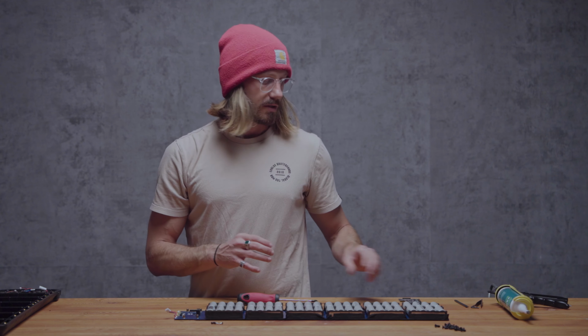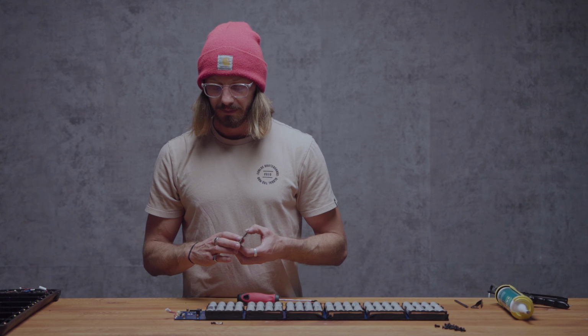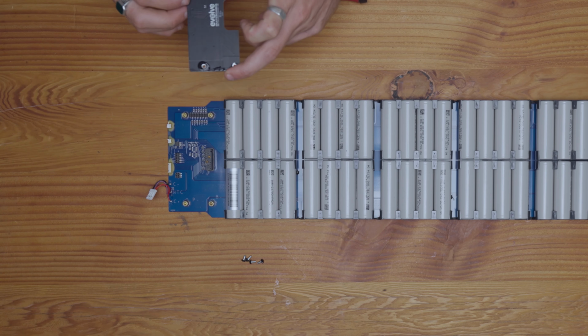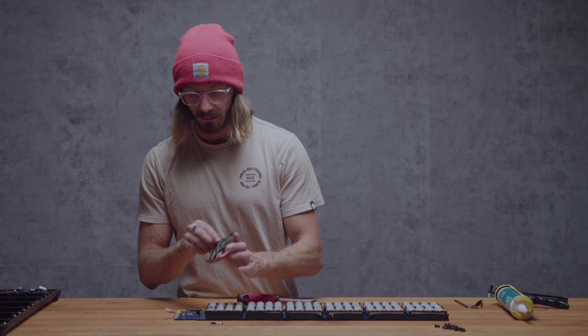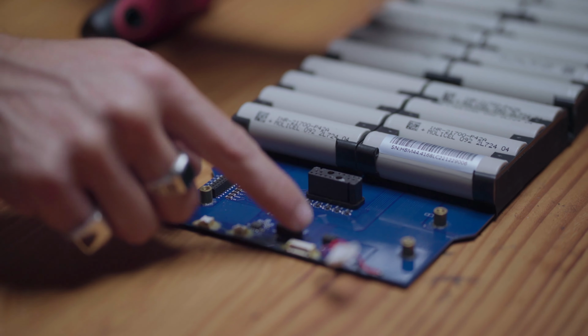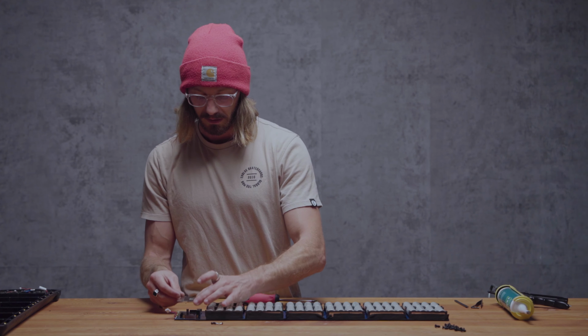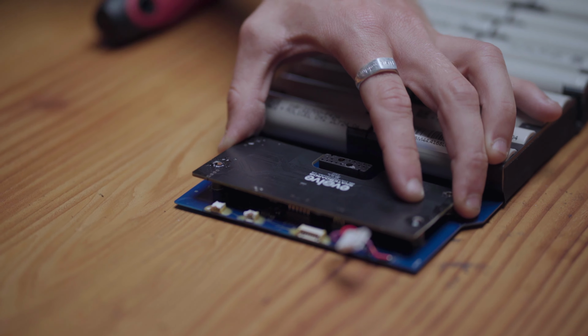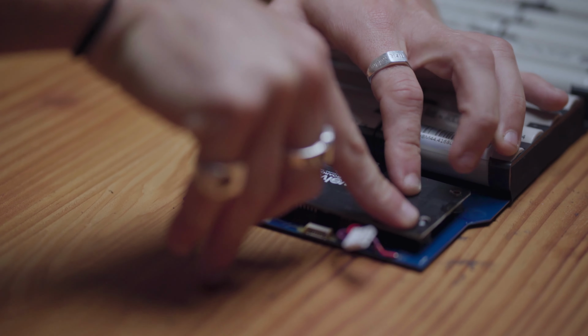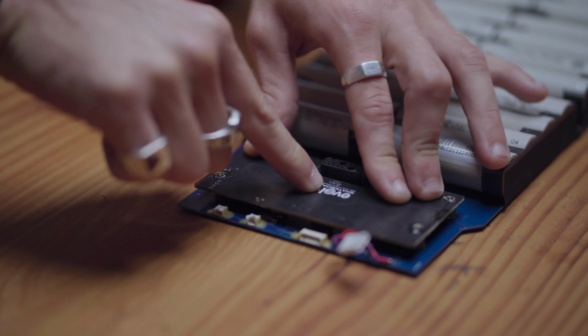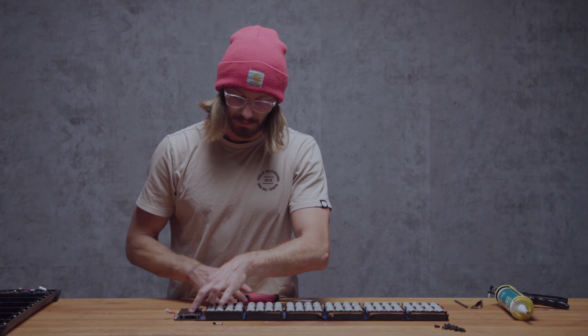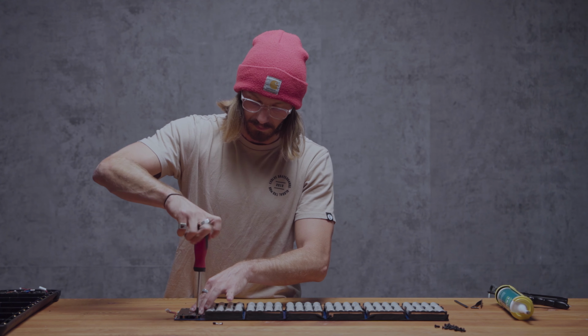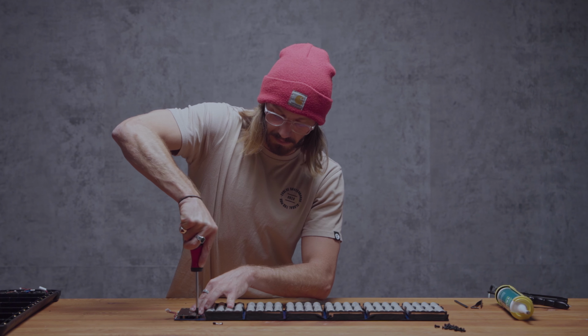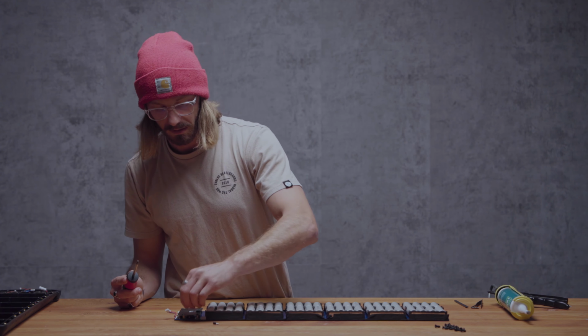So now we're going to go ahead and reinstall our replacement BMS. Essentially the same process in reverse order. First thing is putting the BMS back onto the PCB. Again, we want to make sure we line up all these connectors with the connectors on the battery PCB. Once you can feel they're lined up, have a look to make sure they're lined up properly. Simply push the BMS down to seat it. Holding it in place, we're going to reinstall those 4 screws. Make sure these 2 screws are sufficiently tight because they do carry power through there.